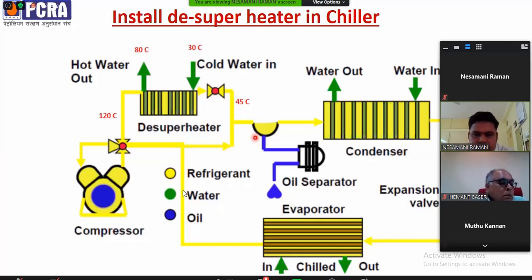At low temperature, they have observed that it was easy to remove the oil, so the maintenance cost of the condenser has also come down, and heat transfer is also very good. As well, the biggest advantage is that because of these low temperatures, the heat load required to be removed in the condenser has come down considerably. It means the fan needed to run a little slower, or the running time has reduced, thereby giving very good power consumption here also. So here we have heat recovery, less maintenance and less power consumption.